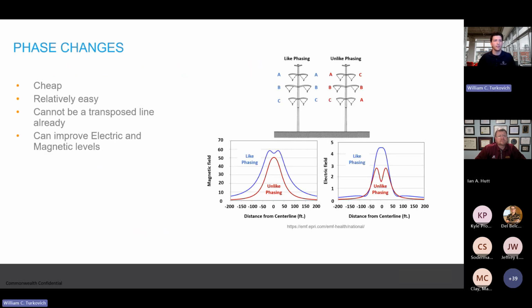The first one would be easy - change the phases. All it is, is routing the conductors in a different order than what you were planning. It doesn't change any different cables, just changes the terminations at the very end of the lines and any tap lines in between. It's relatively easy. It can improve electric and magnetic fields like the graph on the right side. You can actually see it changes the shape and the magnitude of these fields in both electric and magnetic fields, but that's not guaranteed depending on the different characteristics.